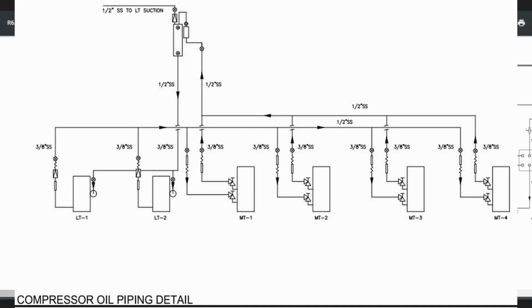So even if you have a little bit of oil coming back through your suction, you're not going to risk damaging it because it's going to be expelled through basically an equalization line right here to make sure it doesn't overfill. Because anyone that's ever worked on a Carlyle knows they do not like oil being overfilled at all. Right. As soon as it gets to half a sight glass, it starts pumping the oil out.